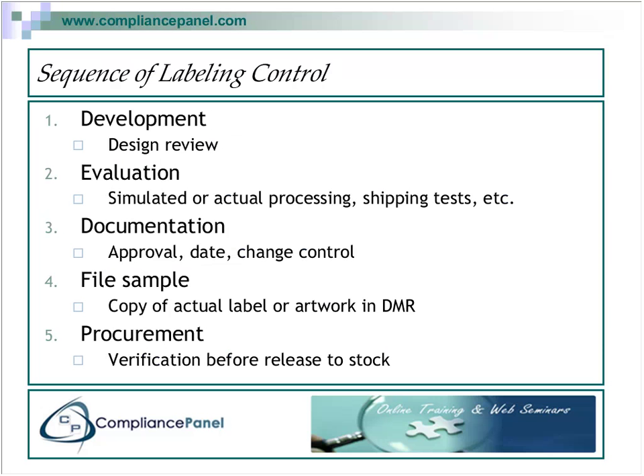Then the labeling is documented. At this point, you know what the labeling is going to read, you know what its characteristics are going to be, and you know that it's going to work. It's going to stay adhered and legible. That's when you approve it via date and change control. All labeling must be change controlled. I recommend that you put a file sample, either a copy of an actual label or the artwork, in your device master record.